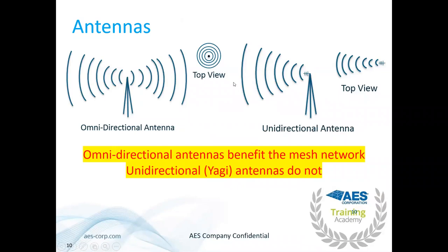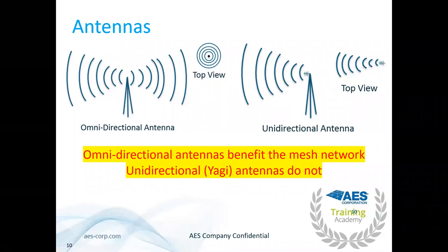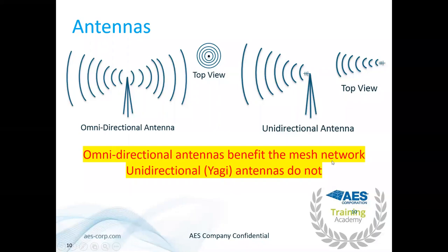For mesh radio networks I would always recommend using omni-directional antennas whenever possible. When using an omni-directional antenna, you want to make sure to get it above the building roofline. I know this isn't always 100% possible, but it will greatly benefit your installation because you're not entirely sure where your next radio peer is going to be located — and even if you do know where all your subscribers are now, you don't know where they'll be in the future. We really want to send the signal in as many different directions as possible.